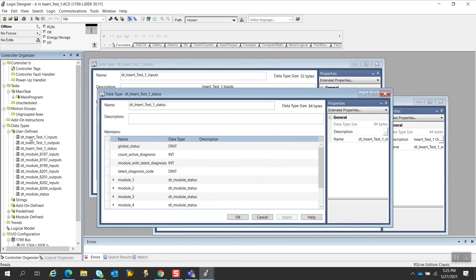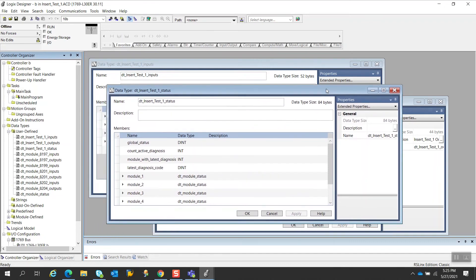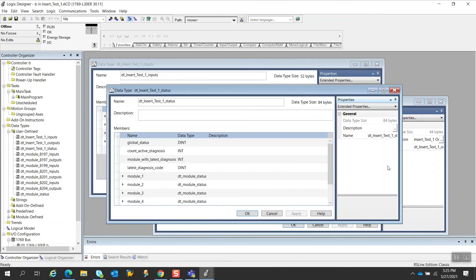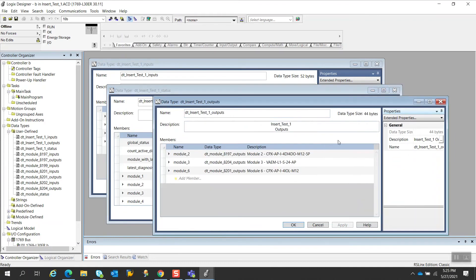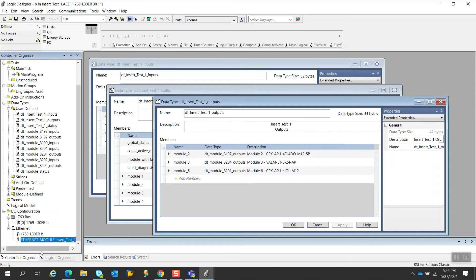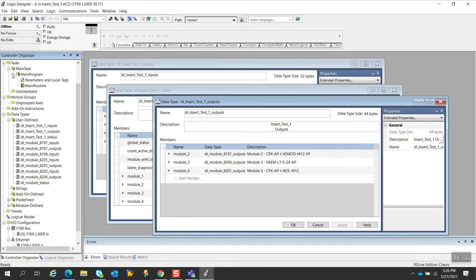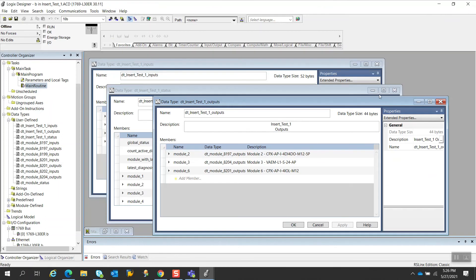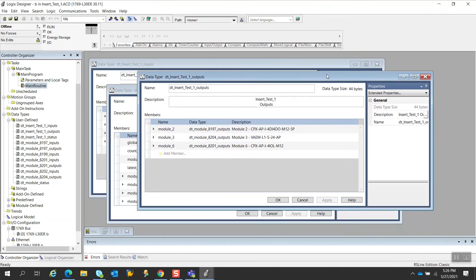If we look at the different UDTs here, you will also see here that the input module, for example, has now this new module two and it's pointing to a 4DI, 4DO module. So, typically when you do this export, the procedure is to copy this module over into your working project and then go to the main routine and select these rungs and export them, and then import them into your project. We're pretty much going to repeat that same procedure with one exception right now. We're going to do a little modification on these three user defined data types, the ones for inputs, outputs, and status.